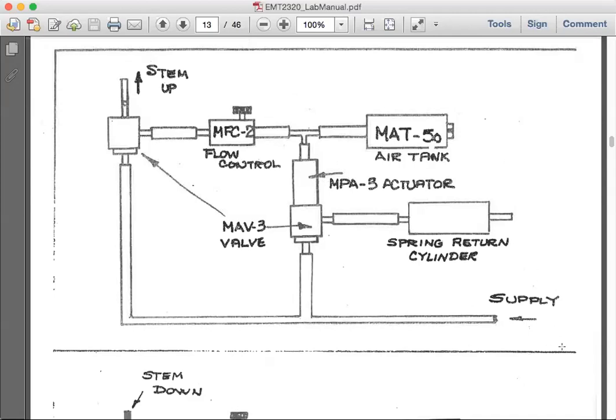So the pressure is about 40 psi, which is a standard pressure for any of our systems. This pressure comes from the compressor, and in the lab it will be indicated on the Bourdon gauge, which is at the beginning of the system. So you would set the pressure and you would log this pressure to have it for the entire duration of the analysis. Okay, so the pressure comes to the bottom of the 3-way valves.